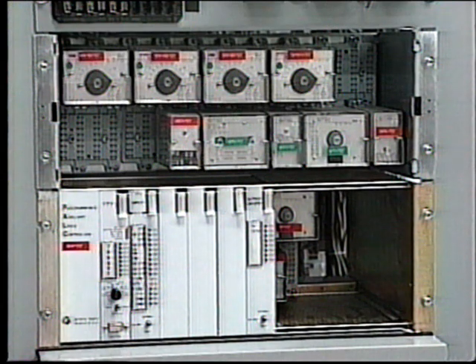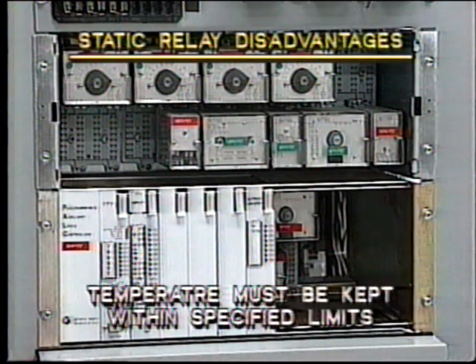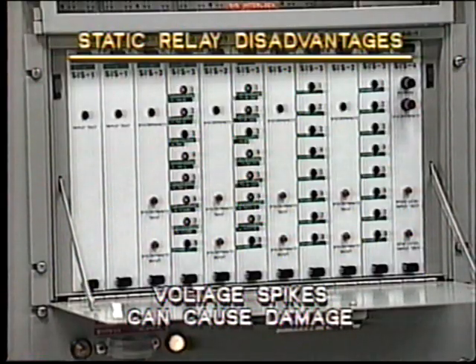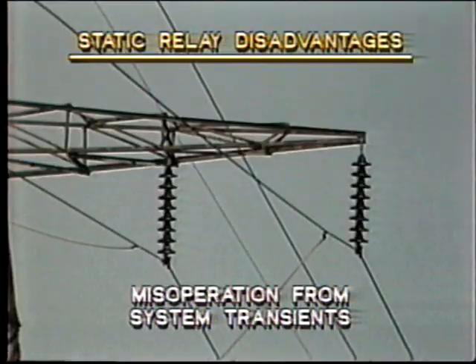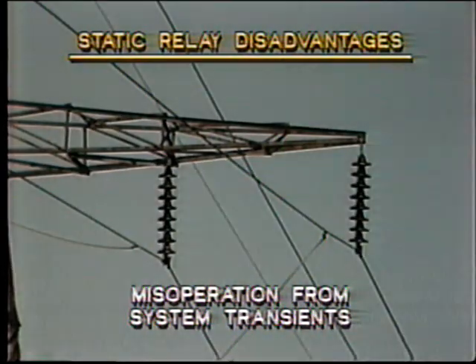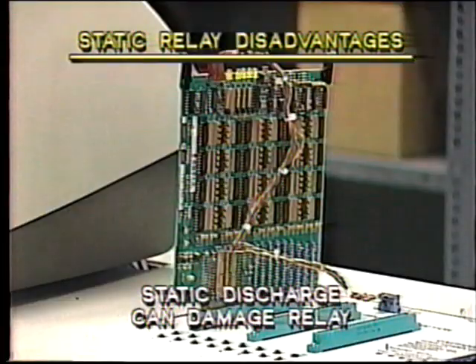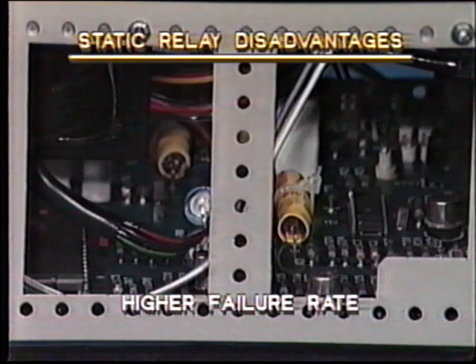As with all such things, there are some disadvantages. Ambient temperature must be kept within specified limits. Therefore, care must be taken with location of the relays. Voltage spikes can damage the relay. It's subject to interference and misoperation from power system transients. Static discharge can damage the relay components during maintenance if the technician and equipment are not properly grounded. Solid-state relays contain a great number of components and consequently a higher failure rate, especially in the first 6 months.